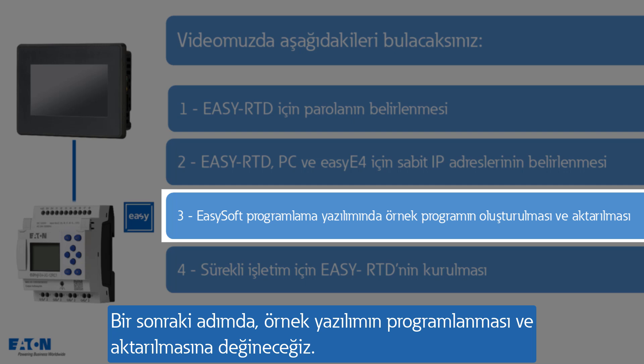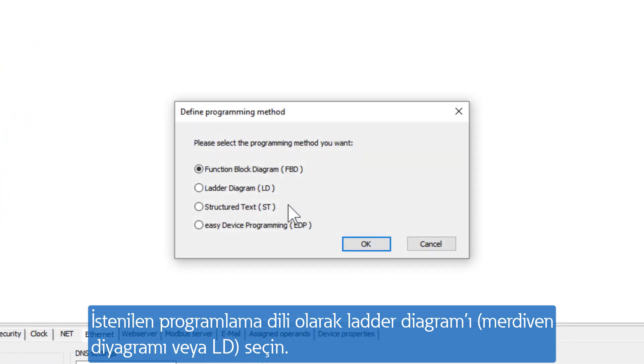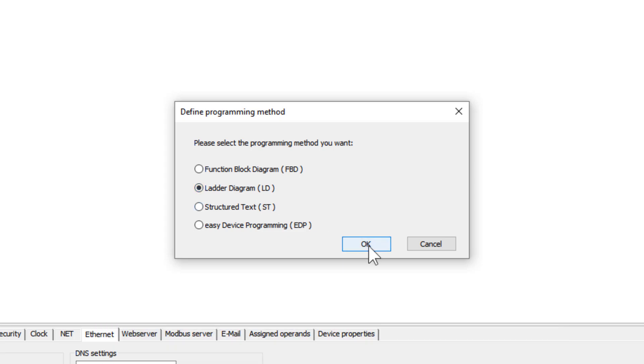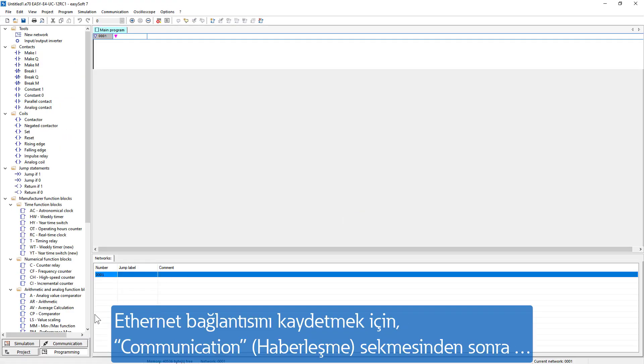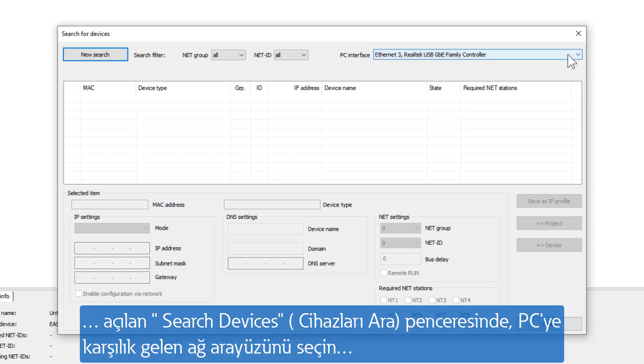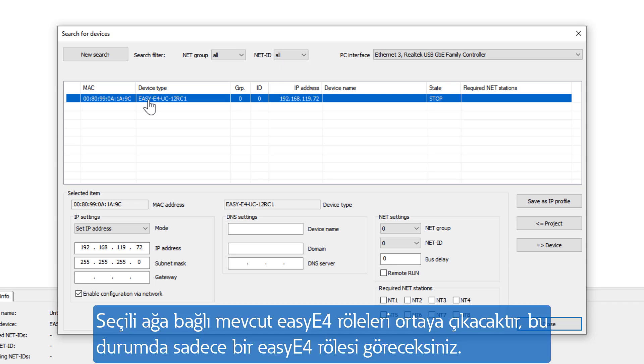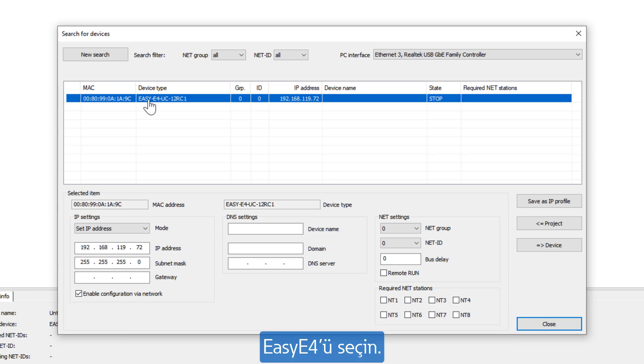In the following step, we come to the programming and transfer of an example program. Select Ladder Diagram (LD) as the desired programming language. For establishing an Ethernet connection, go via Communication to IP Devices, then Search. In the Search Devices window that opens, select the corresponding network interface of the PC and start New Search for Connected Devices. The existing easyE4s in the selected network appear — here, only one easyE4. Select the easyE4.